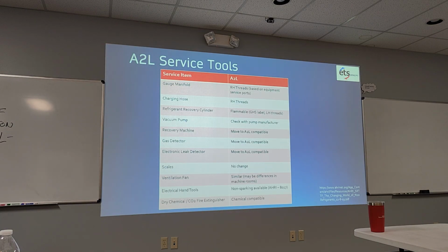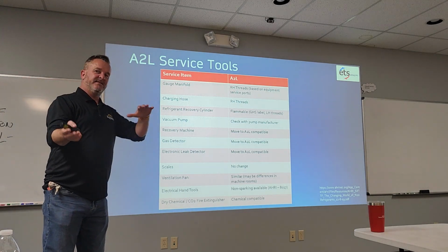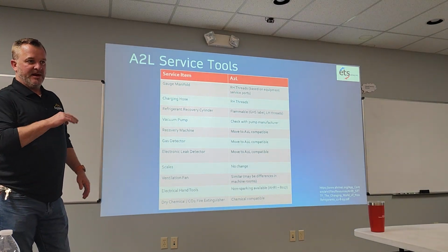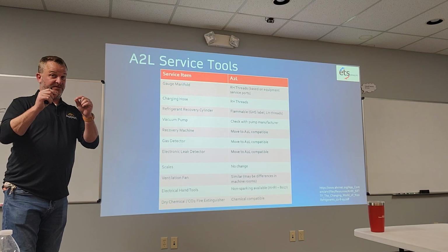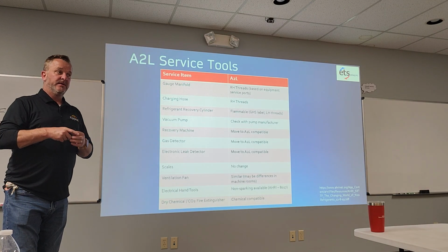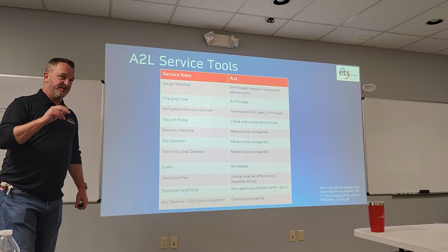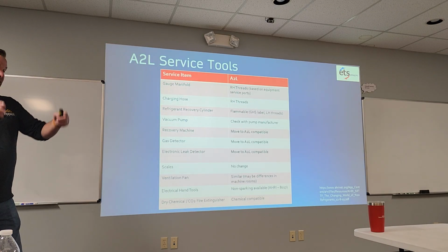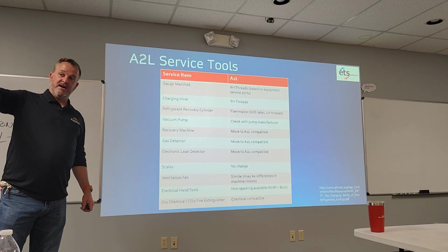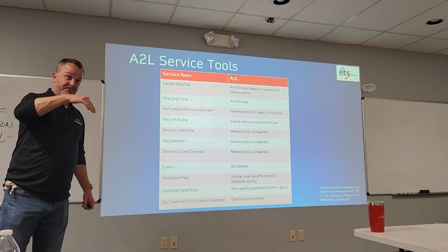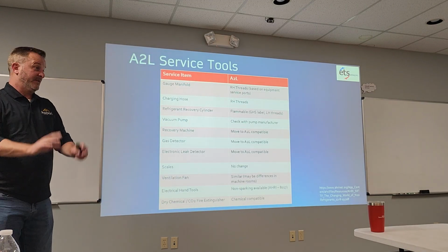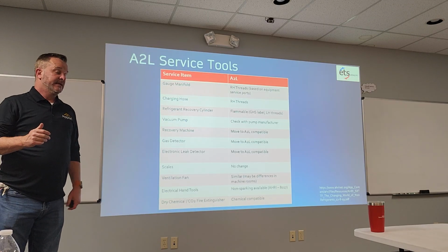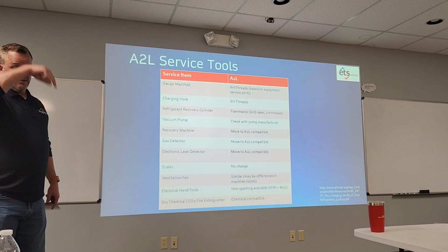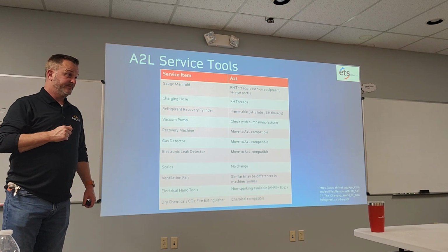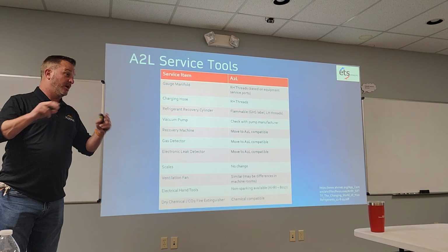Then we get into service tools. As far as I know, I've heard different stances on this. I know that Appian is fully A2L - we're actually A2L certified. We went to UL and did all the A2L testing, and the way they do that is they'll take a recovery machine and put it in a box, then dump propane or butane, which is an A3, in there and let it sit for 15 minutes. They don't do anything to it, and nothing happens. Then they'll do another test where they put it in that box, dump propane or butane, and turn a switch on. Nothing happens, and then they're A2L certified.